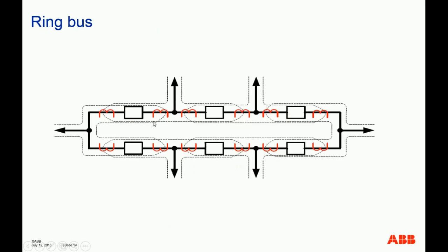For ring bus, basically there are the same number of breakers as the number of feeders or loads. And also there's no dedicated bus bar. Actually, all these bus stubs can be protected by the equipment protection, so it can be a transformer, reactor, or line. These bus sections, as you can see, are actually included in the equipment protection zone. And also, as you can see, all these bus stub protection zones are overlapped.